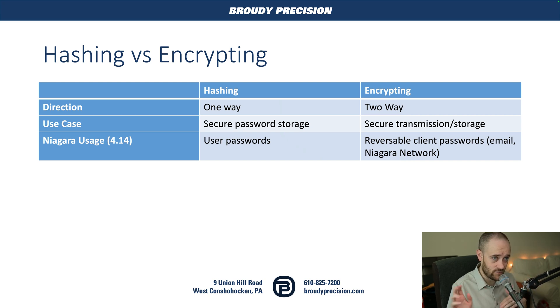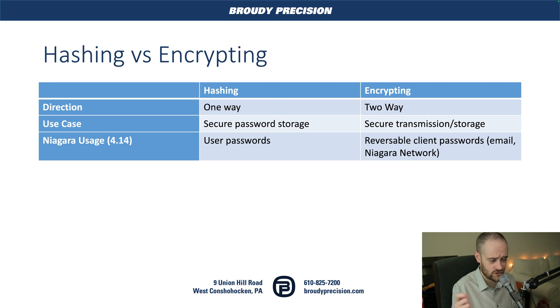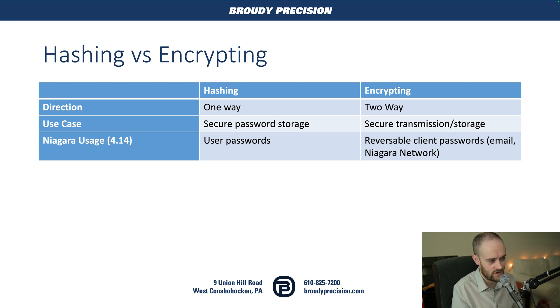Encrypting is different in that we can recover the password — we save it securely, but we need a passphrase or a key in order to get the password or secured information back out. The way this is used in 4.14 and 4.15 is that passwords need to be used for another service, like email or Niagara network. When we're logging into our Gmail server, we need to give it the actual password — that's what encryption is used for here.